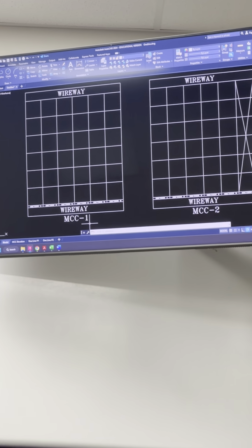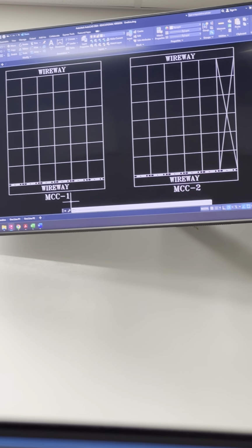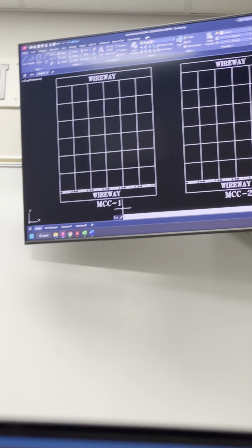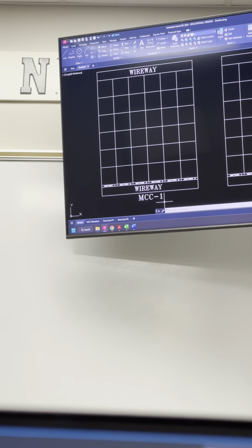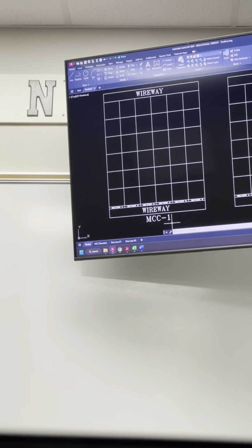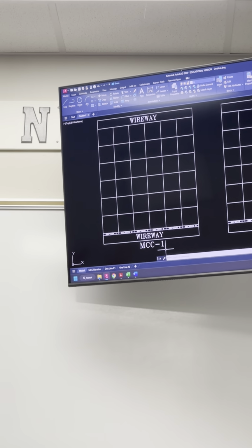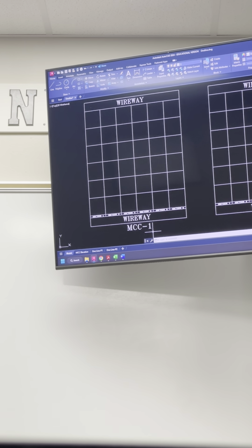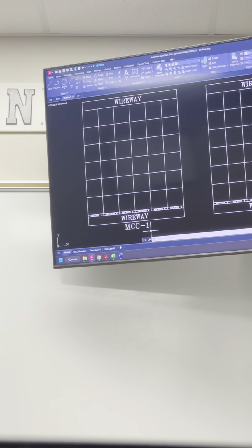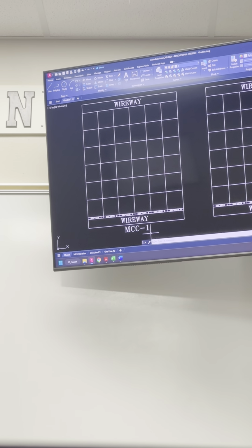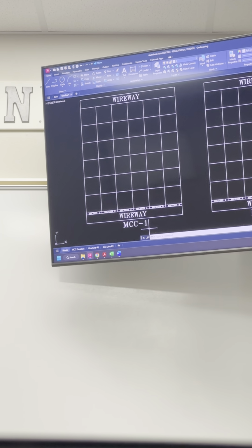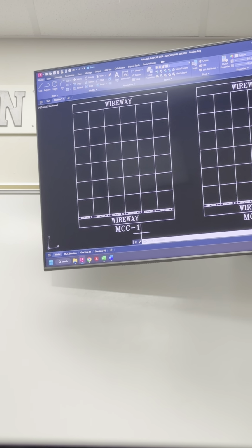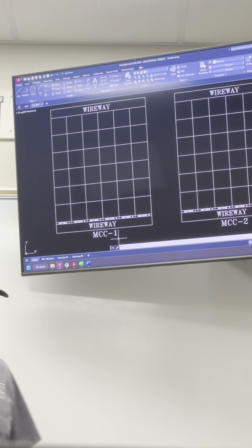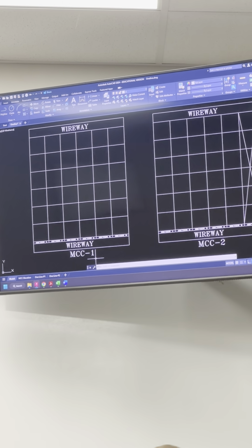Well, we're going all the way up to a 30 kVA, so it's gonna be pretty heavy. So where we put this in our MCC section matters, because these MCCs are about the same size as the ones in your machines class. We don't want to put this 30 kVA transformer at the very top, because that's a lot of weight suspended in the air to install, which makes it more difficult and a little less safe. So we're going to keep that weight at the bottom, and put our transformer in the bottom portion of section 6.